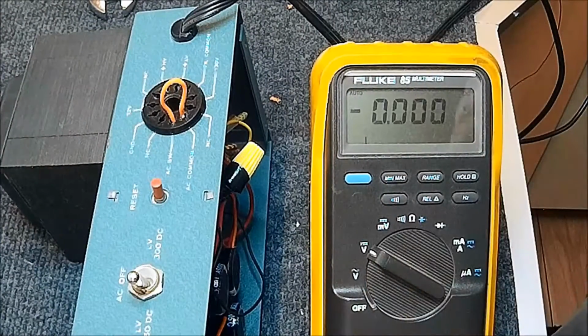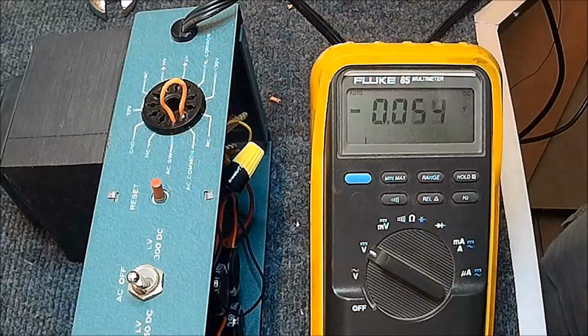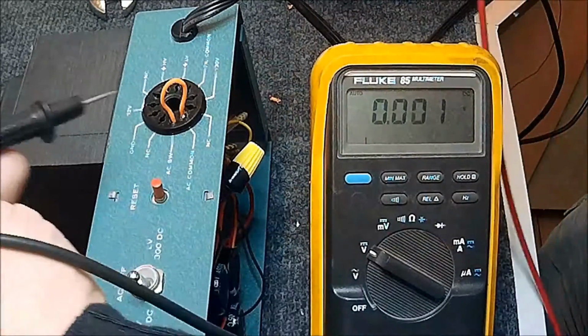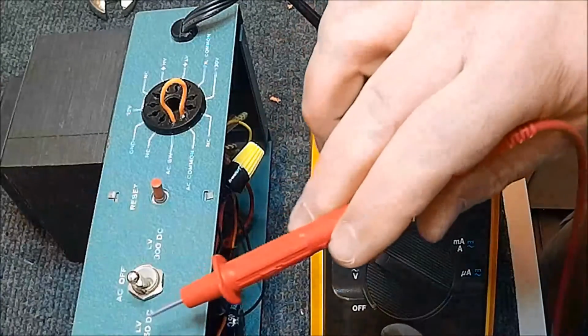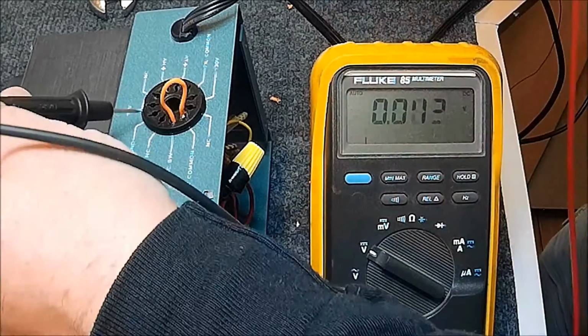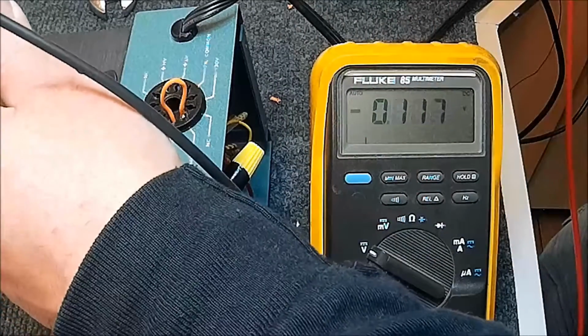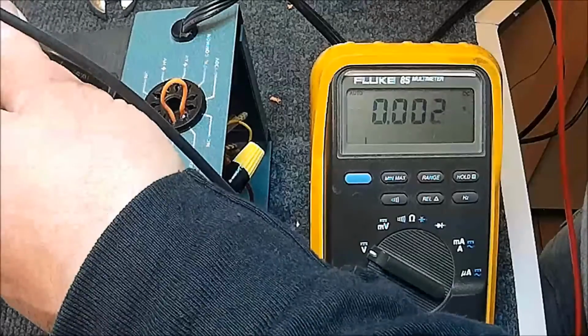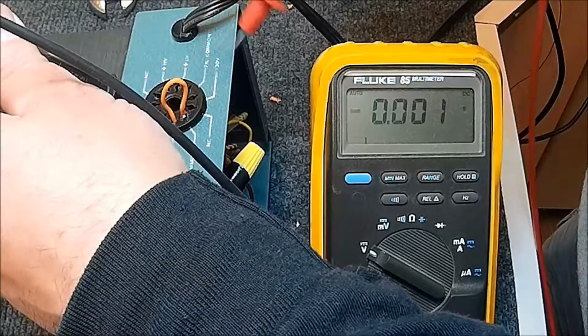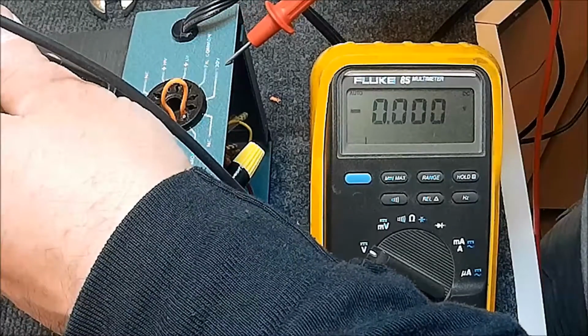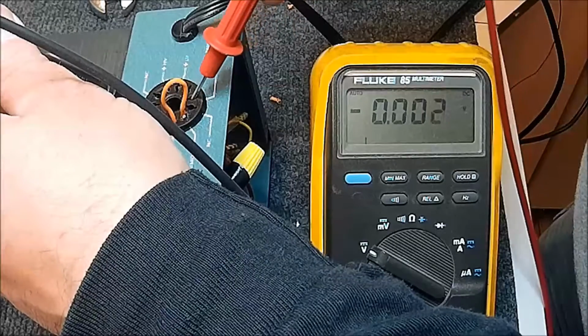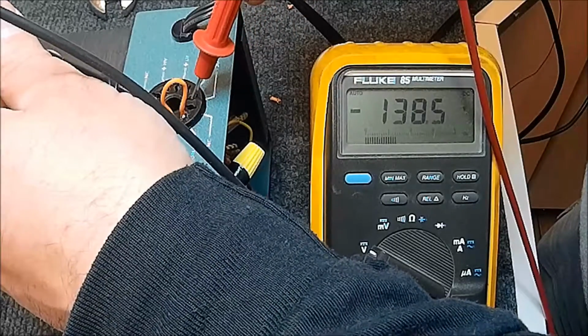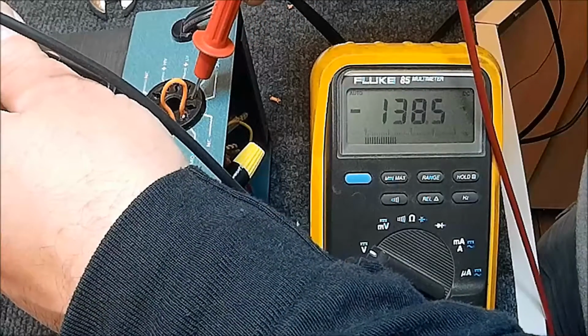Now we'll go to our DC voltage, testing from this ground point, switched to the 250 volt setting, which is actually 275. Put the probe inside there. First I'm going to check the 130 volts DC tap. There we go, 138.5 volts DC.